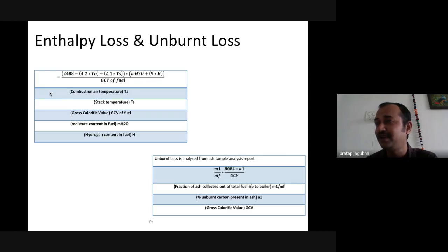That is very difficult to remove, and the moisture leaving from the combustion is also taking the heat. So this is what we can do: we can stabilize the stack temperature within the limit. So that's the advantage of 0.2-0.3% in the loss.